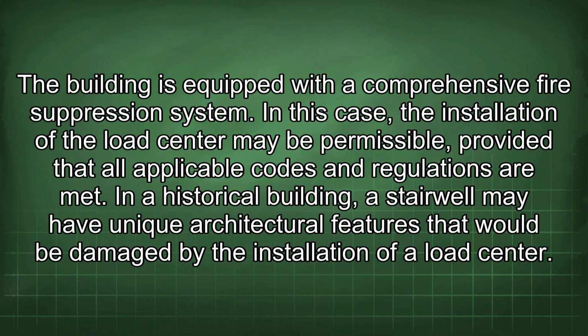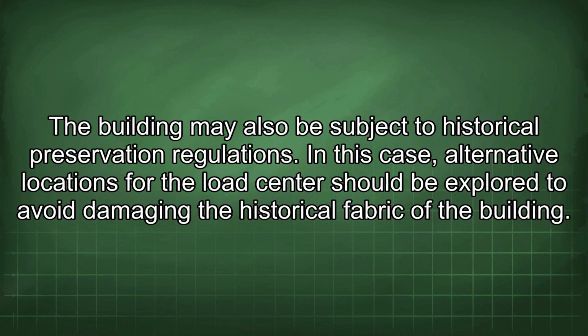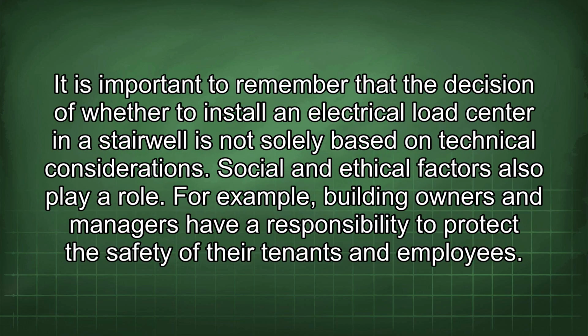met. In a historical building, a stairwell may have unique architectural features that would be damaged by the installation of a load center. The building may also be subject to historical preservation regulations. In this case, alternative locations for the load center should be explored to avoid damaging the historical fabric of the building. It is important to remember that the decision of whether to install an electrical load center in a stairwell is not solely based on technical considerations. Social and ethical factors also play a role.